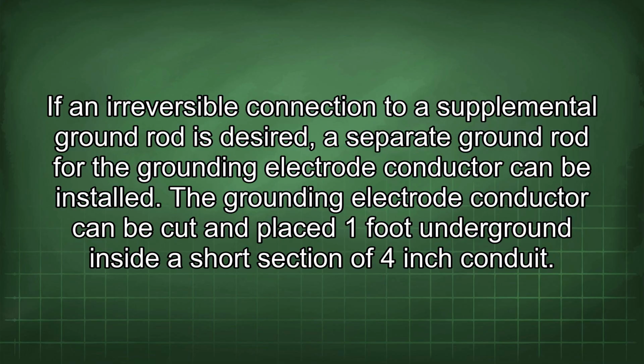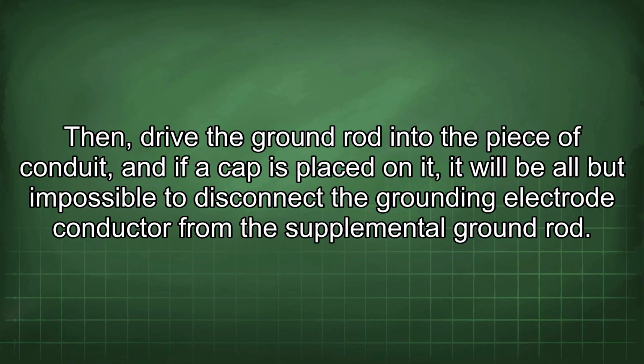The grounding electrode conductor can be cut and placed 1 foot underground inside a short section of 4-inch conduit. Then drive the ground rod into the piece of conduit, and if a cap is placed on it, it will be all but impossible to disconnect the grounding electrode conductor from the supplemental ground rod.